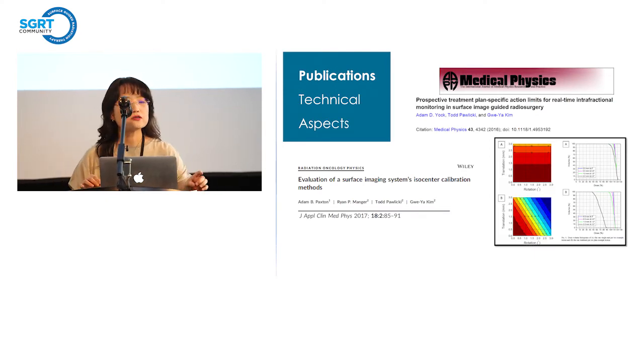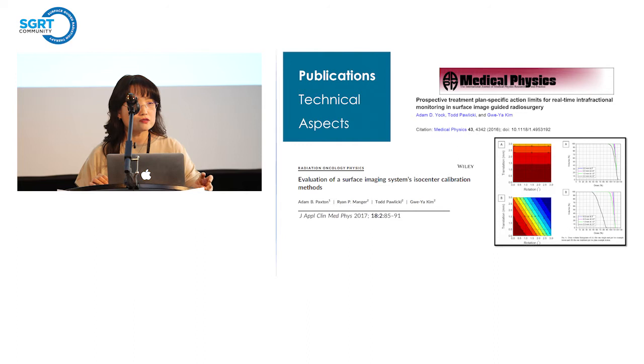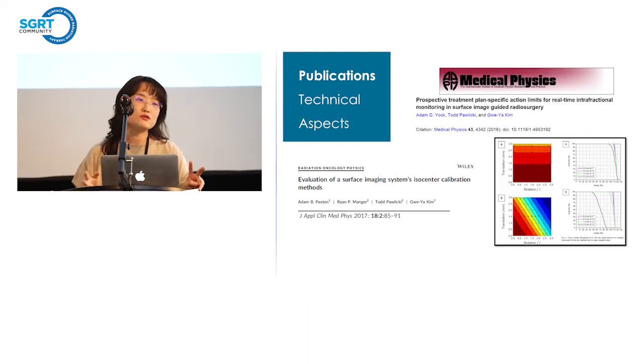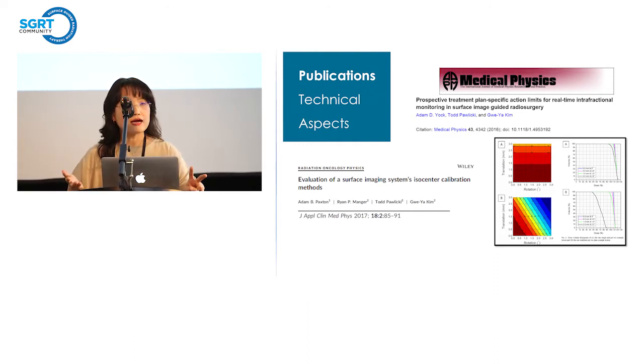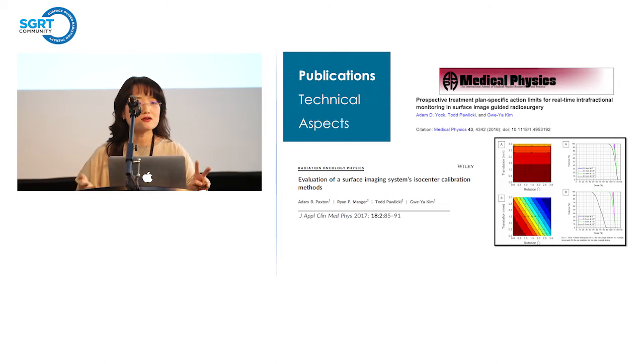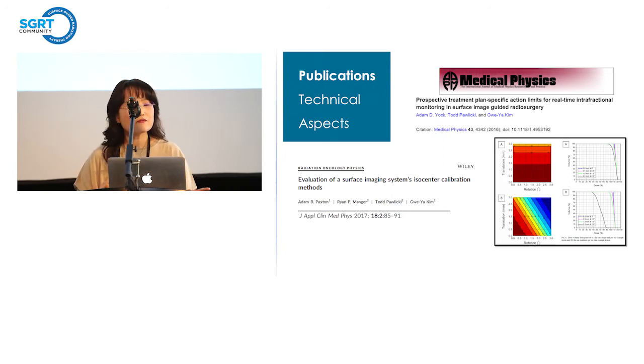The third part is the technical aspect. We have published two recent studies. We have a lot from 2009 and 10, where Laura Cervino published many preliminary studies with the AlignRT system, and this is a recent study on the isocenter calibration. If you're a current user, you might know the isocenter calibration module for the MV-ISO versus the camera isocenter calibration is a great tool. You can catch any minor detail problem and fine-tune to your beam isocenter.